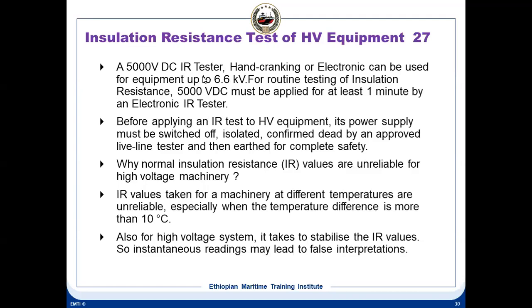A 5000 volt insulation resistance tester, hand cranking or electronic, though you will not find hand cranking, most of them are electronic, can be used for equipment up to 6.6 kV. For routine testing of insulation resistance, the megger must be applied for at least 1 minute by the electronic tester. Whenever you measure normal insulation, you have to apply the megger for at least 1 minute. Before applying the IR test to HV equipment, its power supply must be switched off, isolated, confirmed dead by an approved line tester, and earthed for complete safety.